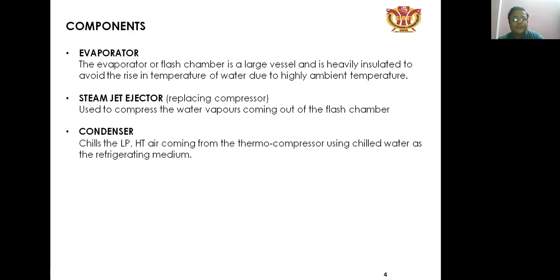What are the components of the steam jet refrigeration system? That is the first, the evaporator. Evaporator or flash chamber is a large vessel and is heavily insulated to avoid the rise in temperature of water due to the high ambient temperature.